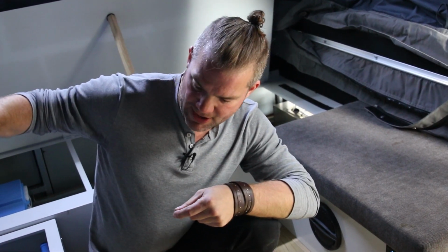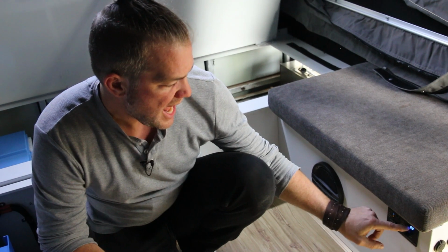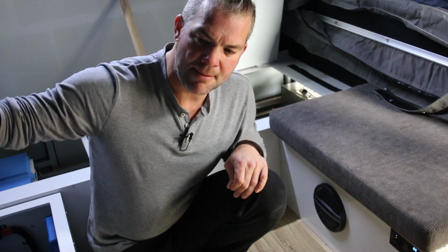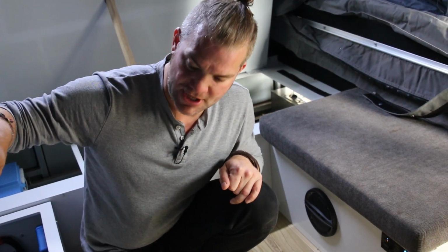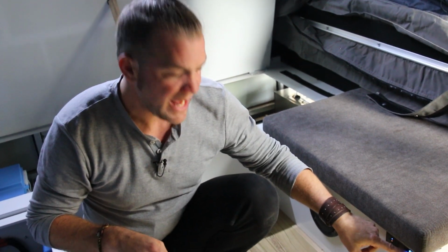If you draw more power because you've got external power now and you plug in your hairdryer, or whatever else draws a lot of power, you might go past 2000 watt, which would stall the generator. But if you've got this dialed down to 8 amps maximum import, or even a bit further to 7.5 to be safe, you won't import more than 2000 watt from your generator. In a peak load condition where you draw about 3000 watt, within a split second the inverter will switch from battery charger back into inverter, called power assist mode.